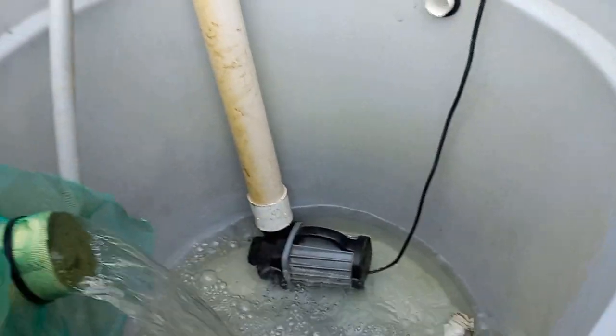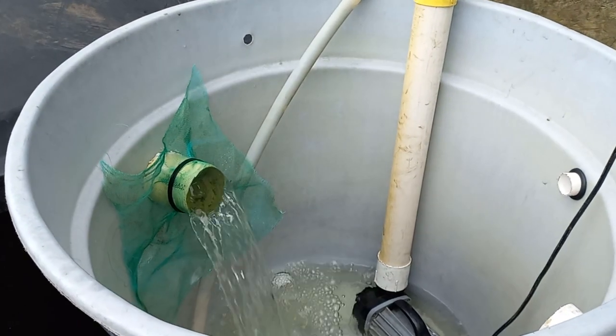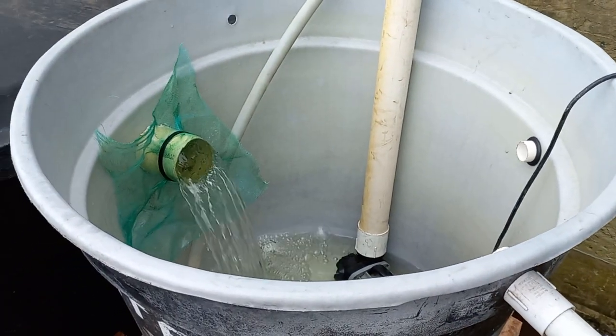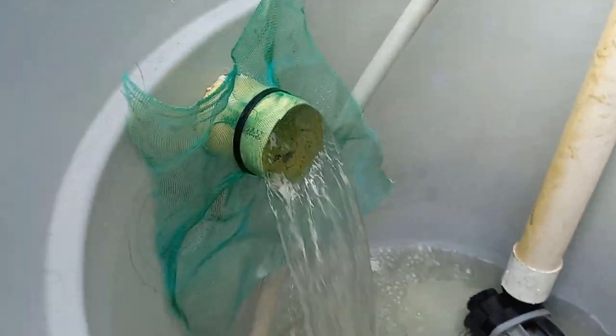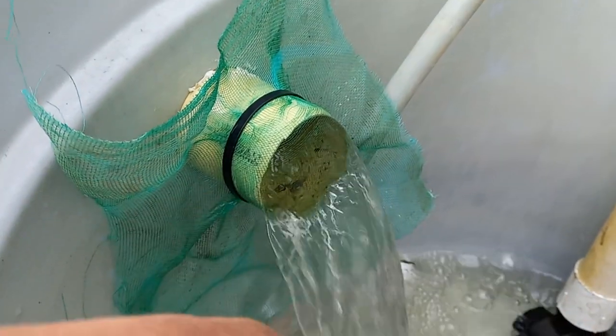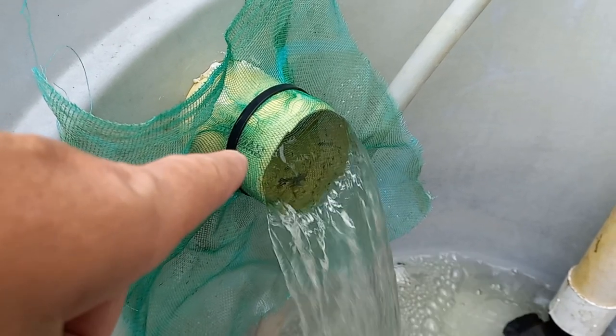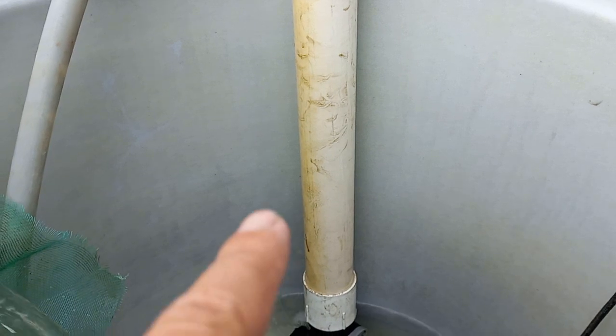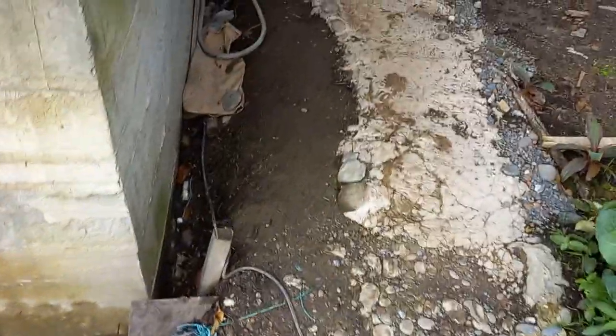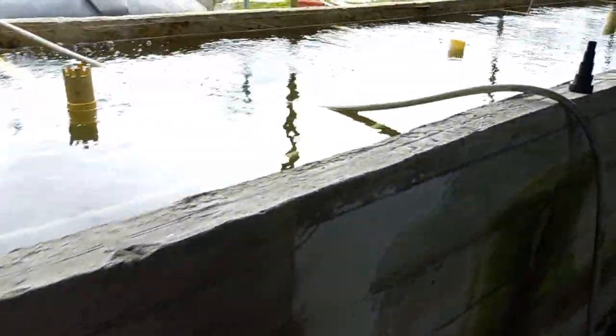I had it hooked up wrong — I was experimenting anyway, and it ended up overflowing a lot. But now I've got it back to the way it should be and it seems to be working perfectly. I just did some math on the amount of water this is loading into this tank: it's about 20 liters in 6 seconds, and this is putting out 20 liters in 6 seconds, so that's about 12,000 liters per hour, or 3,000 gallons. I know most people don't do liters much, but that's what we do here. So anyway, there's your update.